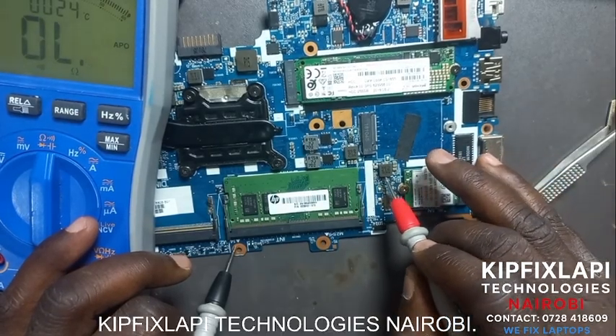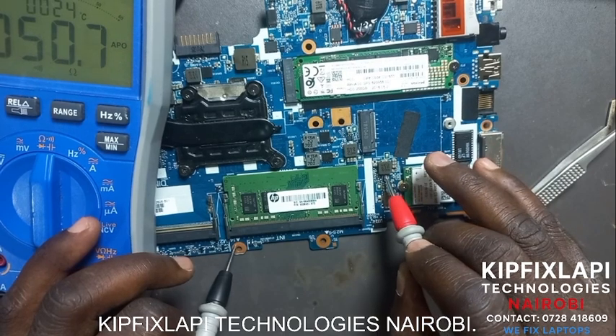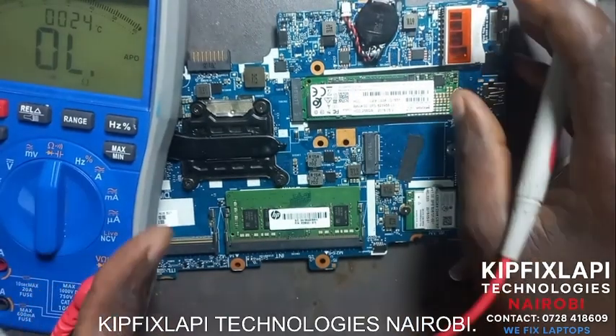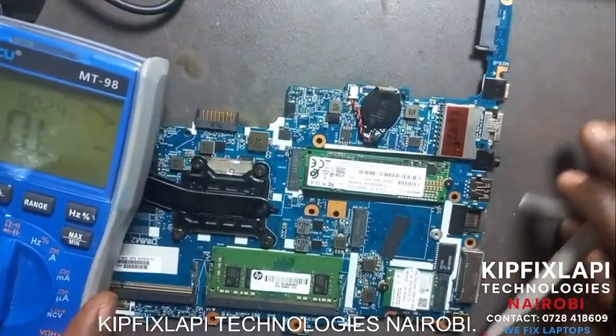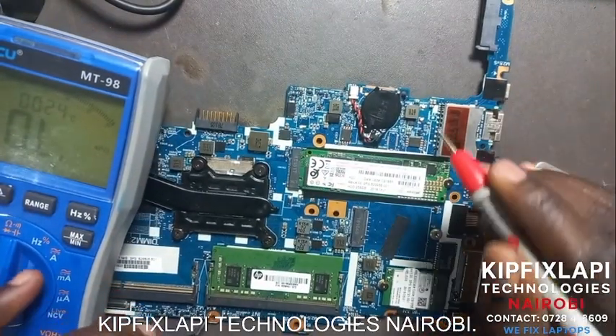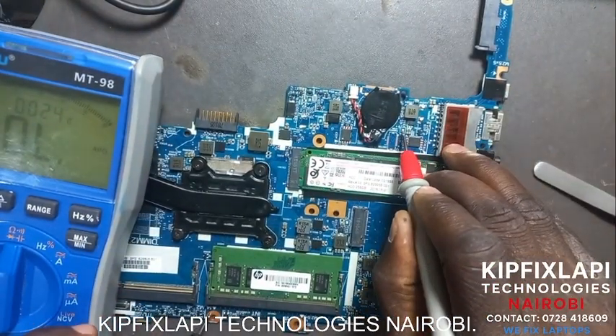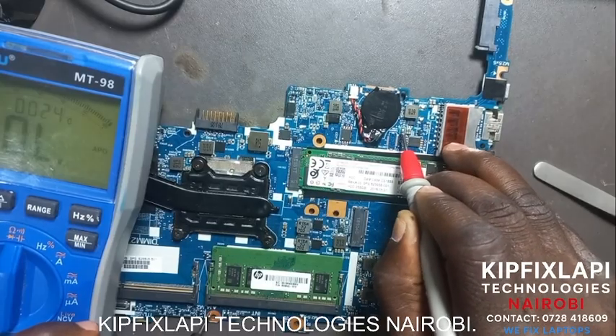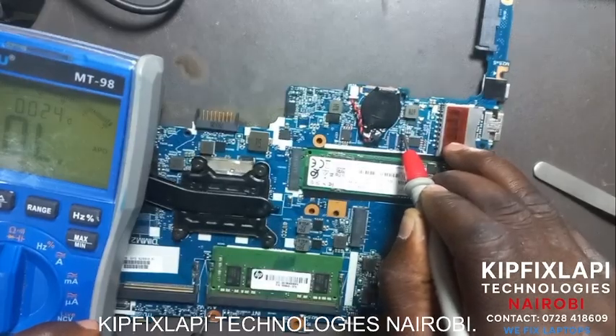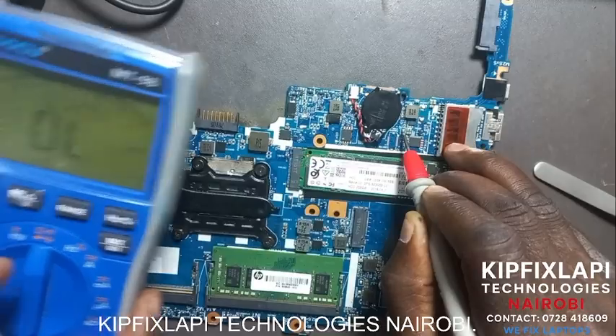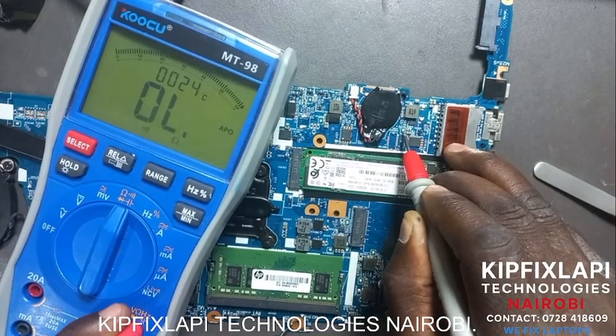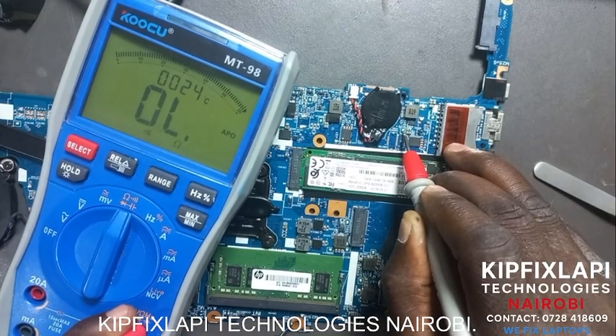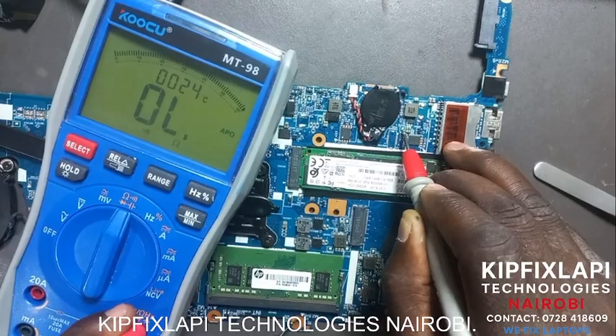And actually, no more shorts. Maybe it's still hot, but you can see we have 50 ohms, maybe the problem is fixed. Let us check the main power line - any input line should be the main power line. And actually it's reading OL, meaning the short is gone. So the problem is fixed.